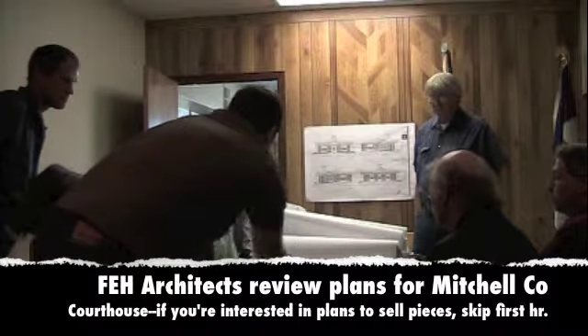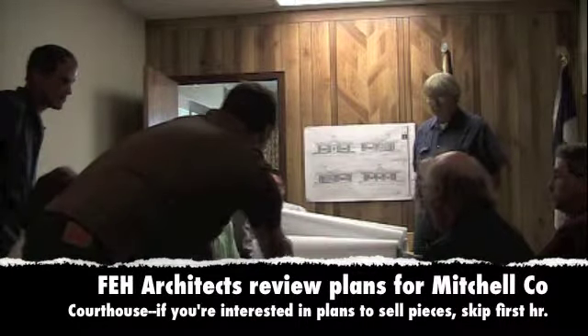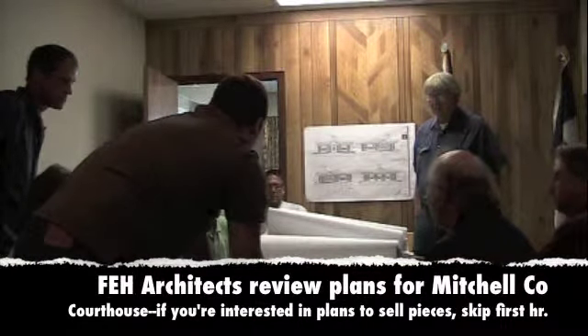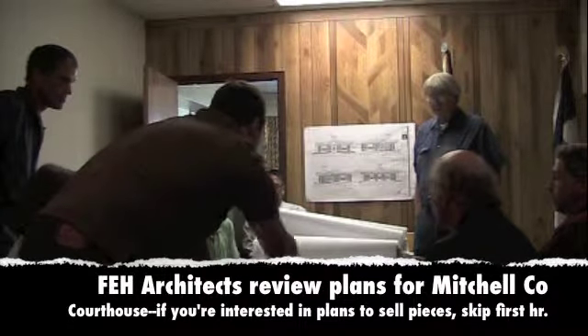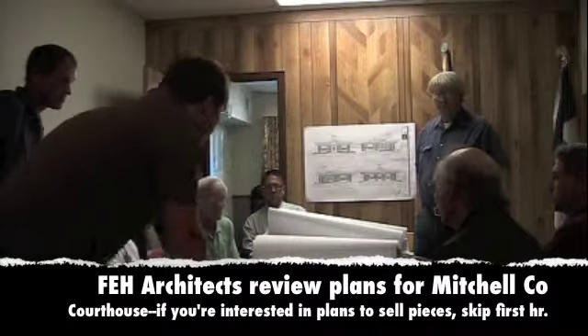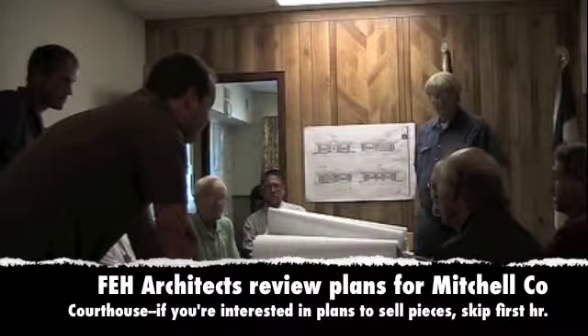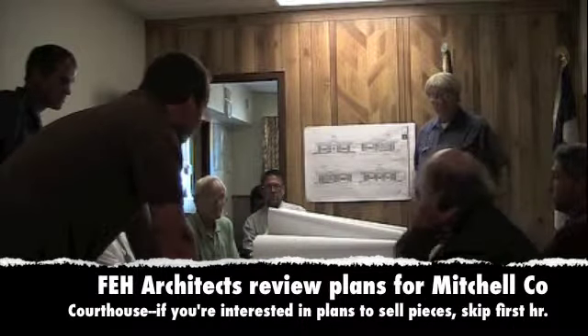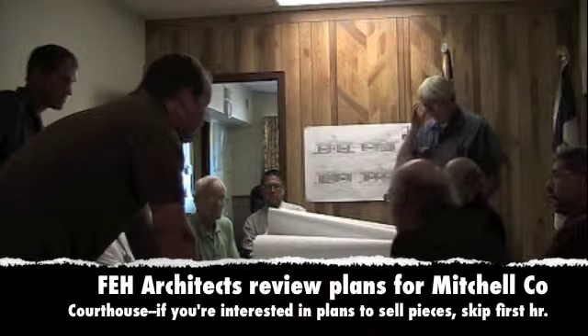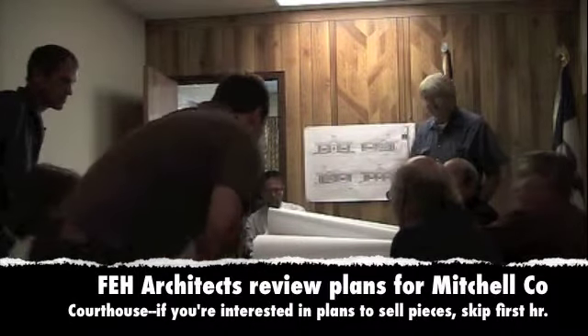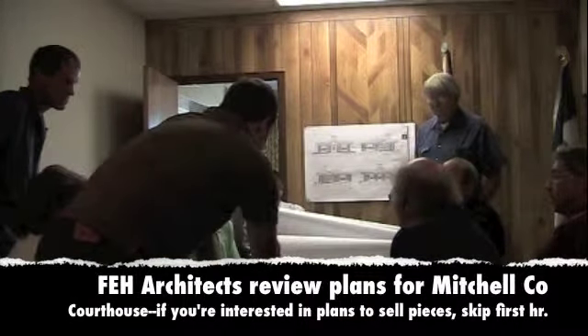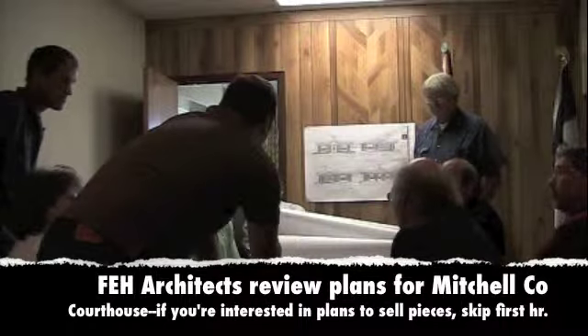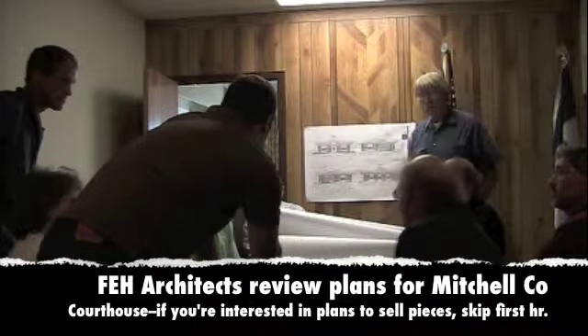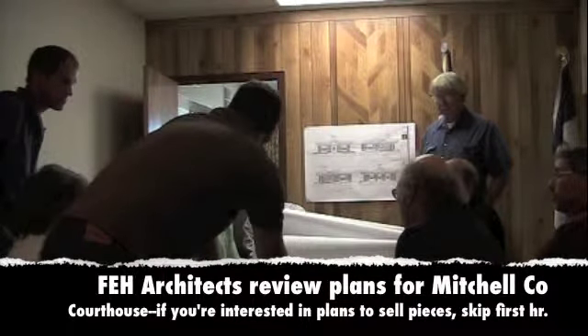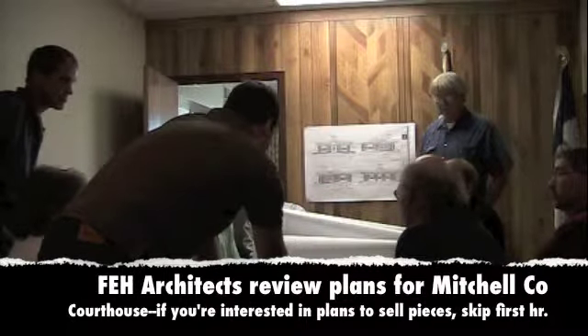In the vault, this is an exposed cassette unit, and I can provide cut sheets on these so everybody's familiar with what they look like. At this point, we're trying to keep them small and as efficient as possible. We've eliminated a lot of the ductwork because of these individual units. And all the piping goes back to the condensing units back here. The piece that's not shown is that each of these units will have two small pipes. The sizes vary based on the exact size of the units, but they're less than 1 inch.